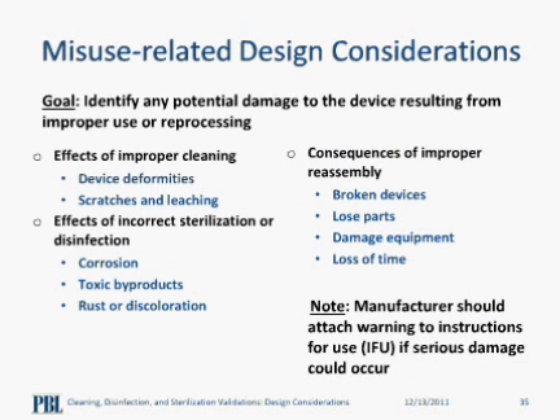What happens if improper cleaning is performed? Well, the device might be deformed, screws may become loose, it may result in scratches, and can lead to leaching of device materials. Likewise, if an incorrect disinfection or sterilization process is used, it may result in corrosion or toxic byproducts might be released. It can also lead to other physical changes like discoloration and rust formation. Consequences of improper reassembly include breakage of the device or loose small parts. This may cause damage to important equipment in use, and subsequently, loss of time to reprocess can happen.